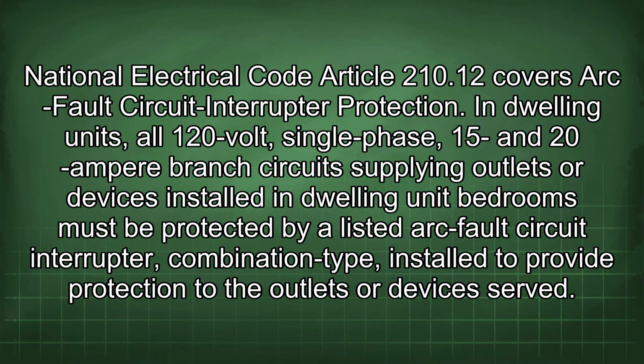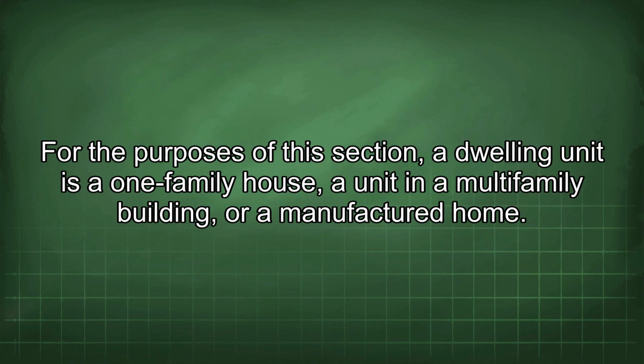National Electrical Code Article 210.12 covers arc fault circuit interrupter protection. In dwelling units, all 120-volt, single-phase, 15 and 20 ampere branch circuits supplying outlets or devices installed in dwelling unit bedrooms must be protected by a listed arc fault circuit interrupter combination type, installed to provide protection to the outlets or devices served. For the purposes of the section, a dwelling unit is a one-family house, a unit in a multifamily building, or a manufactured home.